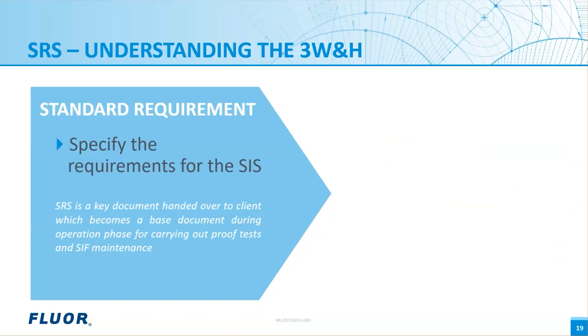For development of the SRS, it is important to know the 3 Ws and H of the SRS. The first W addresses who develops the SRS and keeps it updated. Remember, the SRS is a live document and needs appropriate updates during different phases, and the stakeholders of those phases should understand this requirement. The second W addresses what should be the content of the SRS. Section 10 of IEC 61511 Part 1 is a good guide on the content requirement. You do not have to look elsewhere.